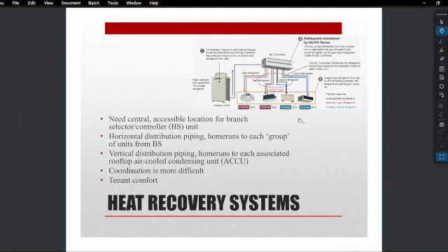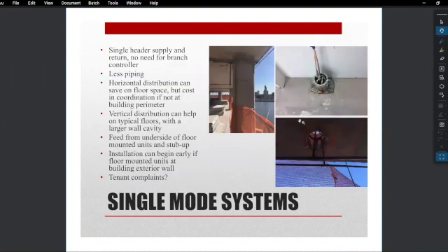So with the heat recovery system, oh, sorry, I forgot to mention one other thing about the single mode. The other problem with the single mode too is if you ever have a refrigerant leak or you need to service or take out a unit completely, once you cut into that refrigerant piping, you're basically compromising everything that's connected to that particular ACCU. So once you break that refrigerant piping open, all that refrigerant has to be recaptured and refilled. So everybody that was on that system would be down in such a situation.